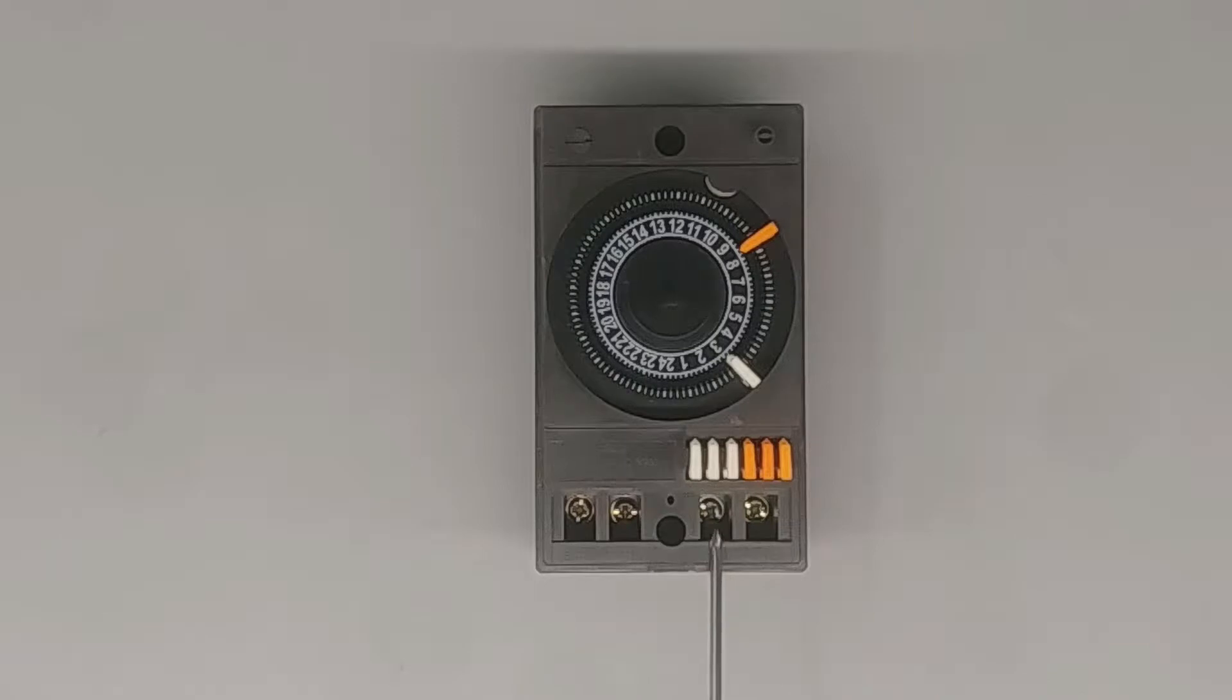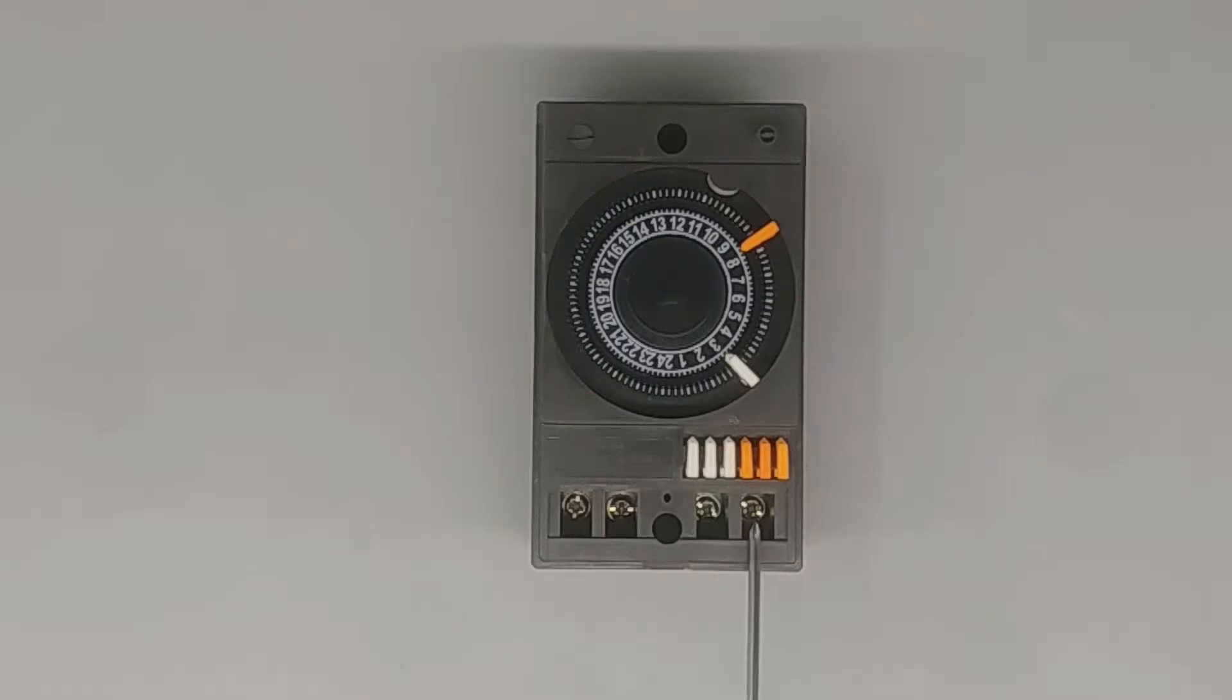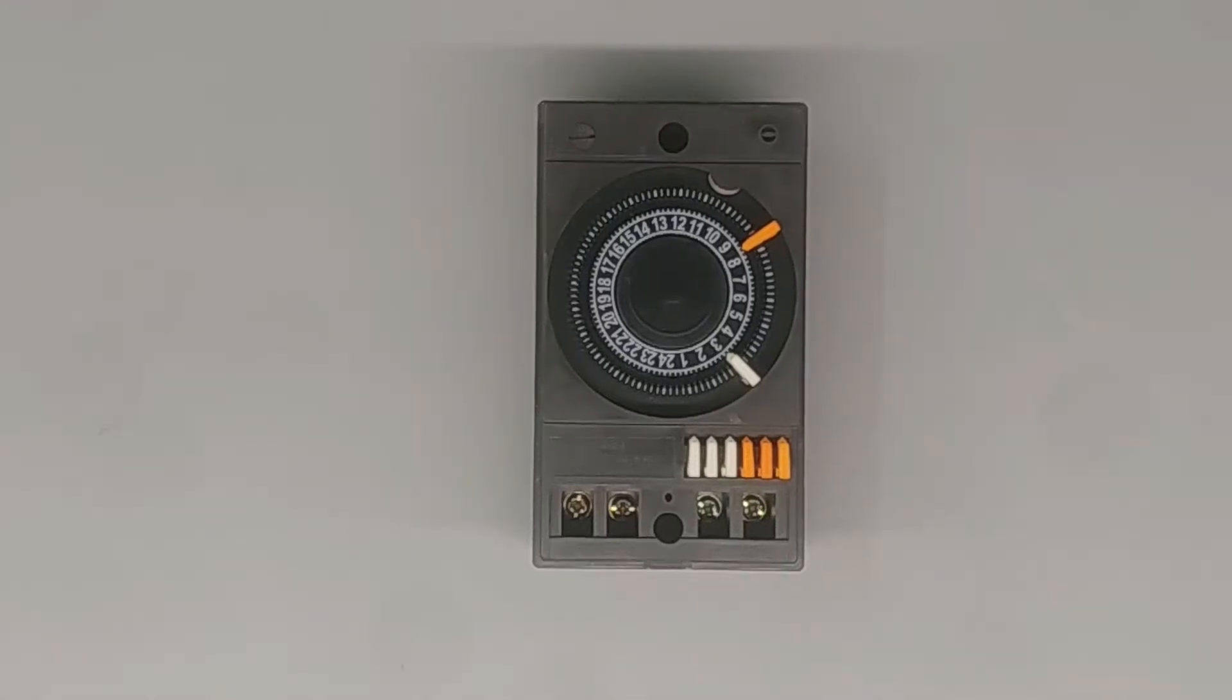What happens with this timer is the neutral goes in here and it's always bridged to this one here. Then the live would go from here and it's switched to go out on this side. So what you're going to do first is connect your live and neutral to these two points.